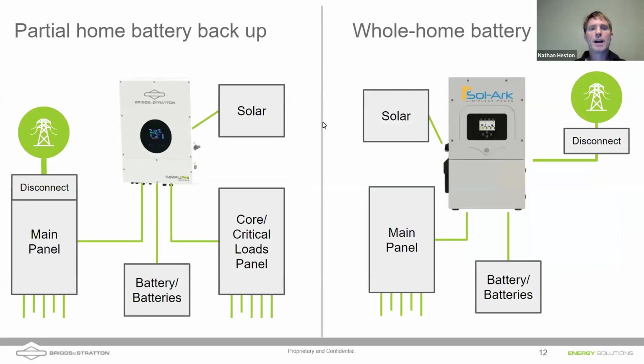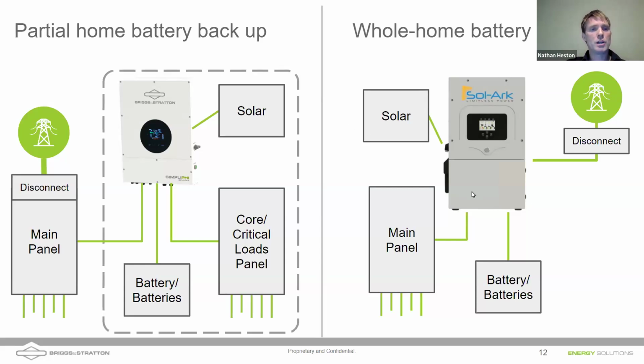So partial home backup: if you look at the left side of your screen, I'm featuring our Briggs & Stratton inverter here. This inverter is smaller. It's a 6 kilowatt output, and it only has 40 amps of pass-through. This inverter is designed specifically to meet the needs where the Sol-Ark is just too big of a unit. And so in a grid down situation, the inverter isolates itself from the grid, essentially disconnects itself from the grid, and that's a requirement of hybrid inverters. And they've been doing this for over 20 years now. I believe the first were doing this in New Mexico about 2000, 2001. So these hybrid inverters isolate from the grid.